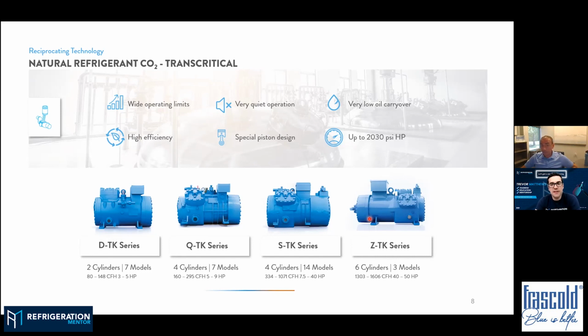Yeah, why don't we talk about that a little bit? Because I see this on almost all CO2 compressor manufacturers. A lot of them have the splash, or most of them do, but when you get up to that 50 horsepower, the bigger ones, they need a pump. Can you explain why that is needed? Well, it is mainly for the distance that the oil has to travel from the place where it is to the last lubricating point. It's like piping. On the small compressors, on a 2-cylinder, it's pretty easy to let the oil reach the crankshaft and the piston rods. But when we talk about a 6-cylinder, where maybe the last piston rod is far away from the injection point, we definitely need some extra pressure on the oil side to reach the last lubricating point.